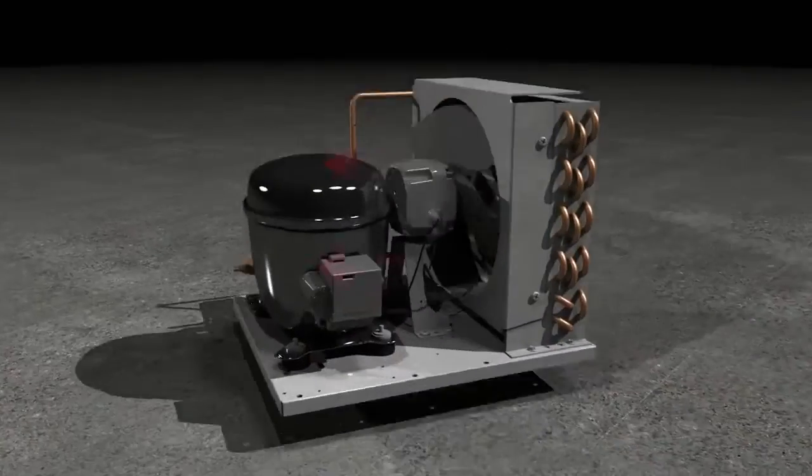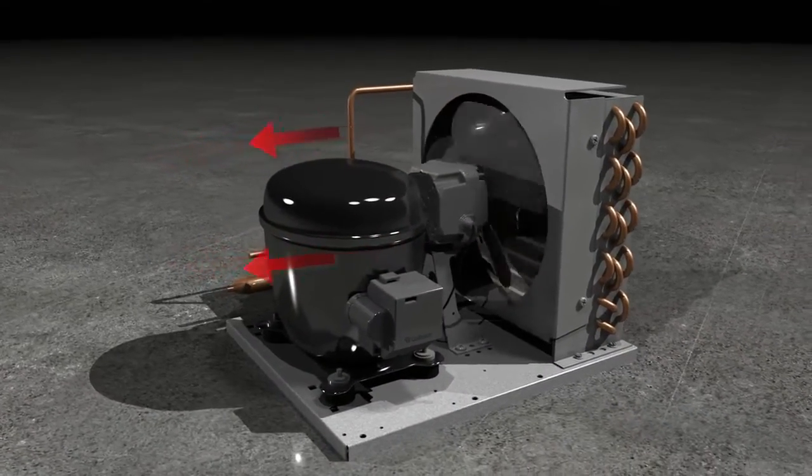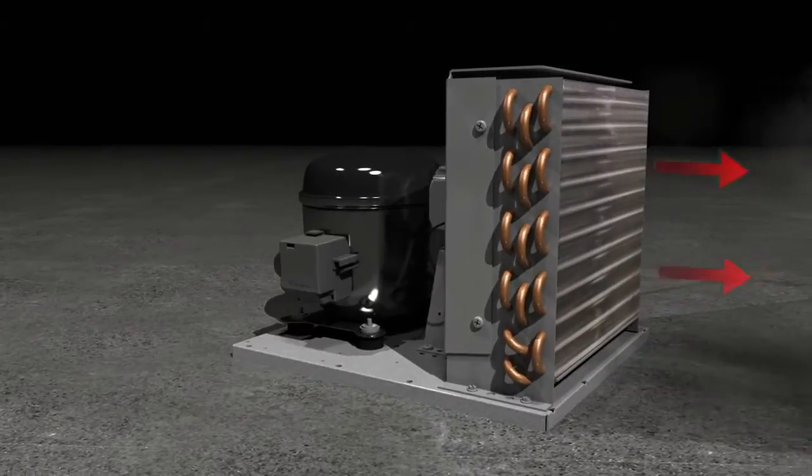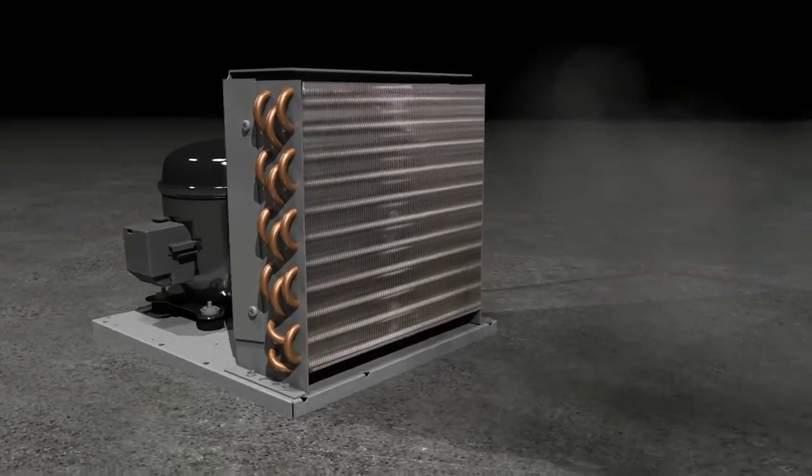RCU technology reverses the direction of the condensing fan motor upon each compressor startup. The fan motor will then help blow off excess dust, dirt, and debris from both the interior and the surface of the condensing coil.